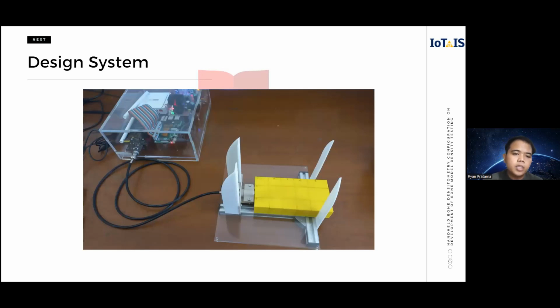Okay, the last part is pulser. To ensure the operability of the system, we need to pay attention to the pulser used. The pulser has an input voltage of 5 volt. Care was taken to set this input voltage to ensure that the pulser function optimally and provides the signal needed for bone density measurement.